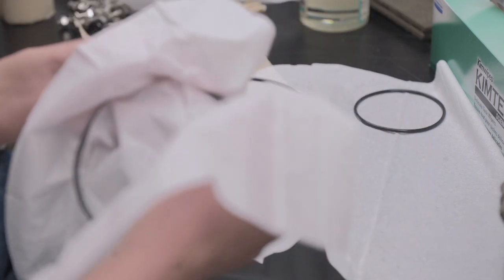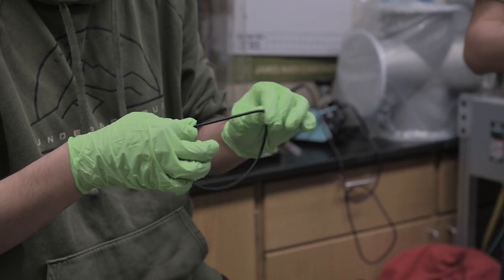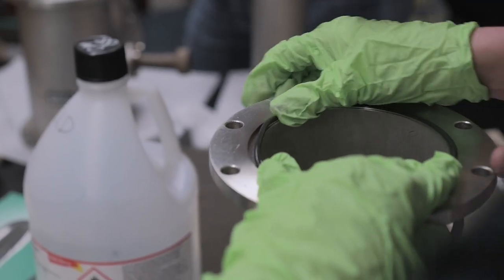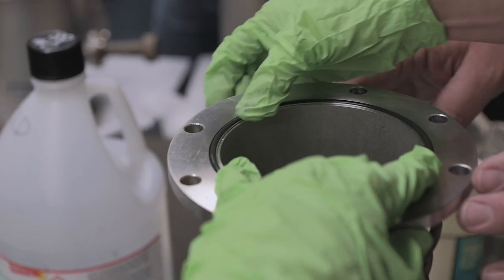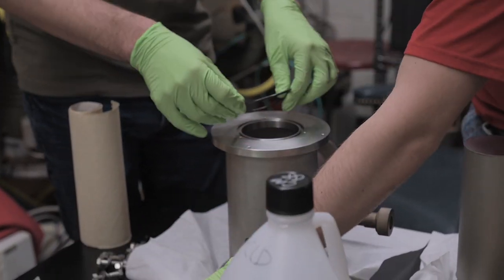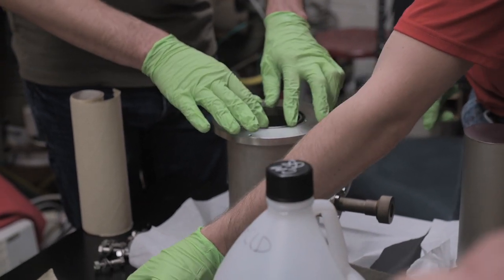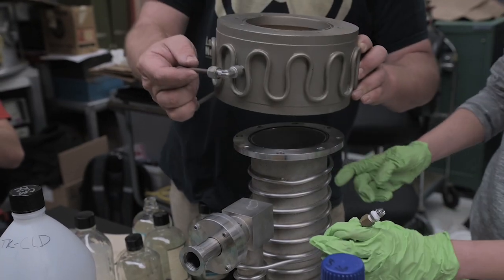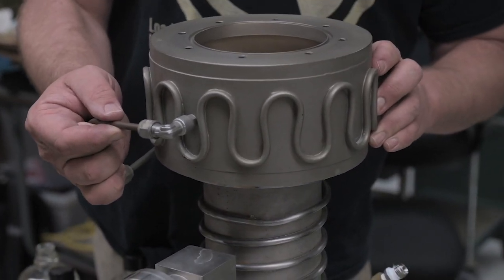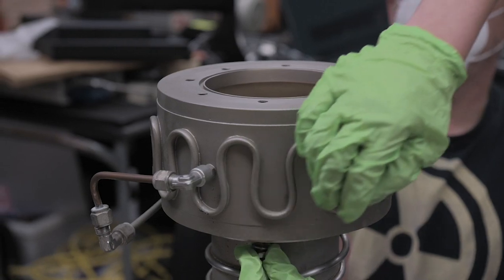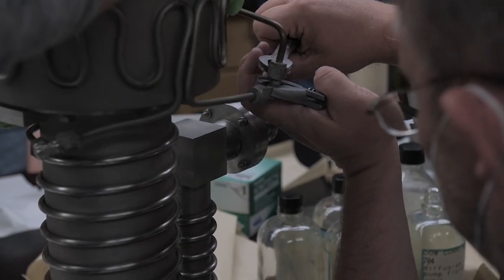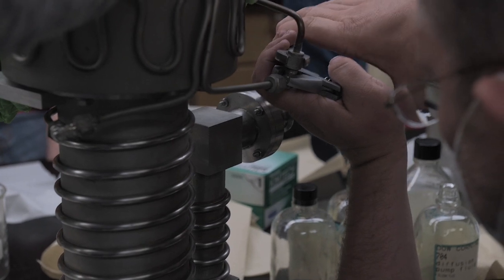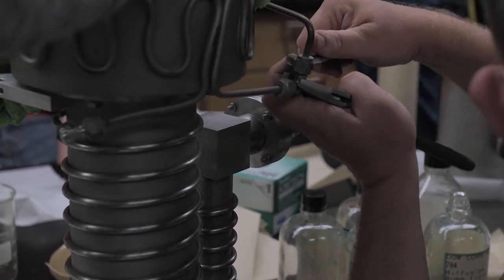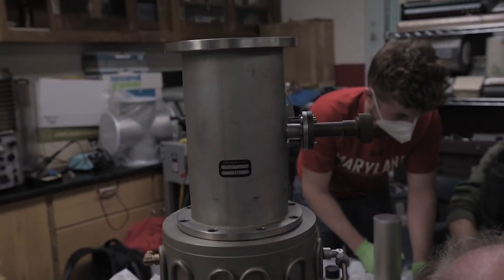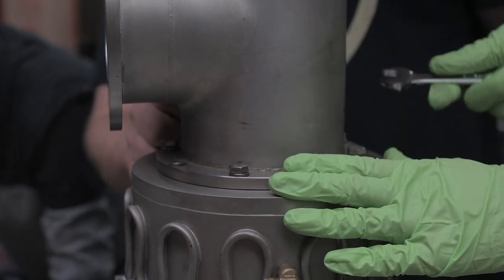Before reassembly, all of the O-rings must be cleaned and coated with a fine, thin layer of Apiezon high vacuum grease. Reassembling the diffusion pump, bolting on the water-cooled baffle, reconnecting the water cooling lines, and attaching the cold trap.